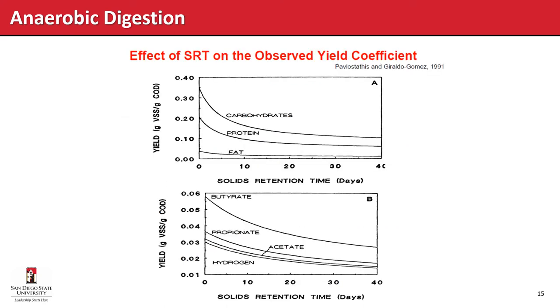A graph comparing carbohydrates, proteins, and fats shows yield in grams VSS per gram COD removed versus solids retention time (SRT) in days. Carbohydrates yield the highest, proteins lower, and fats the lowest. A longer SRT gives a lower yield, which is desirable because it means less sludge to manage. However, longer SRT in a CSTR-type system requires a larger reactor, so there is a trade-off.